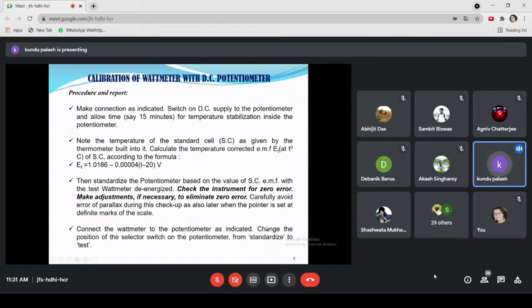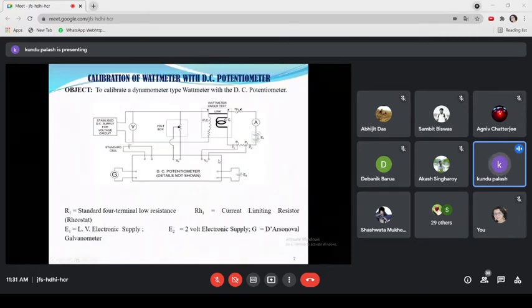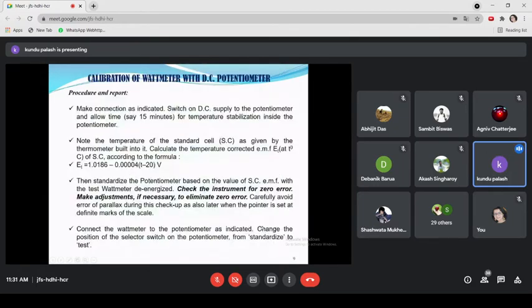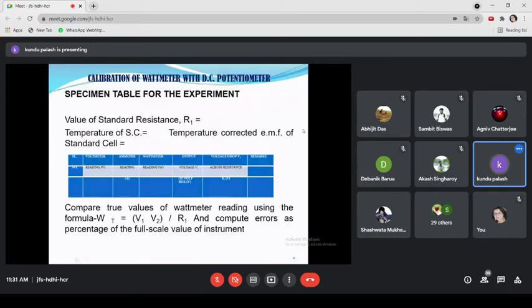So connect the wattmeter, then the standard cell should be eliminated from the potentiometer circuit, and connect the wattmeter to the potentiometer as indicated, according to the circuit. At a time, only V1 or V2 can be measured. That's why there is a selector switch on the potentiometer, standardize and then test. During standardization, the selector switch should be set to the standardize point. Otherwise, in normal operation, the selector switch of the potentiometer must be set to the test mode. I will show the videography so that you can see how the potentiometer looks.